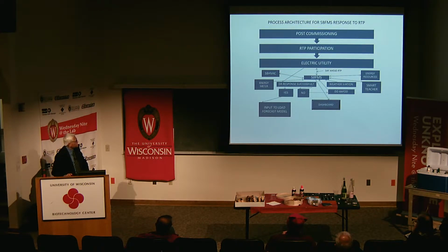If the answer is no, then that means there is possibly a fault. So automatic fault detection and diagnosis, AFDD, is initiated in the smart building HVAC system. And once it determines the fault, the operator can restore the system, or if it's possible to have self-healing and resiliency, it can automatically do it. Now, the process continues.